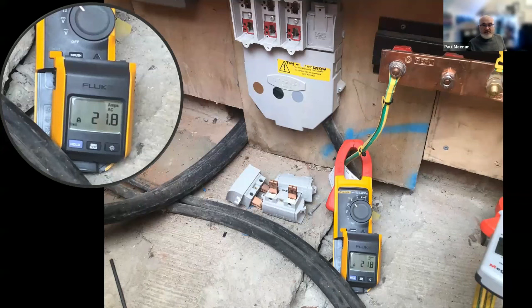One of the scarier images in my collection is where you have the service cutout, which is the gray thing at the top. You have the fuses on the floor, but you still have energy. So I've isolated the installation, or as we call it in England, the disconnection and separation of all sources of electrical energy in such a manner that it's secure, and there's still power flowing. So there's a problem on the earthing. So what can we do? How do we understand that better?